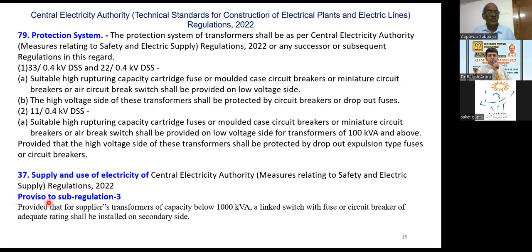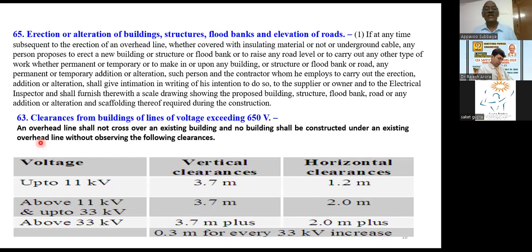You can see as per the proviso to sub-regulation 3, for suppliers' transformers of capacity below 1000 kVA, the linked switch with the fuse or circuit breaker shall be installed. So we have to collate all these things and send a note to the concerned authorities to check whether these are incorporated. Since a lot of electrical questions are recently coming to the picture, another thing is the consumer's responsibility.